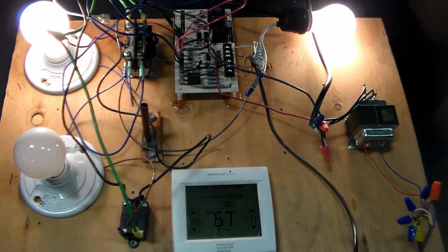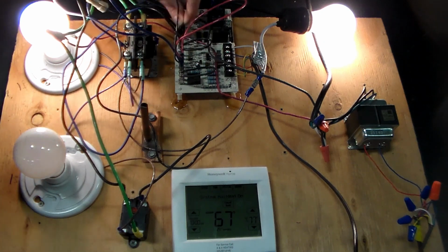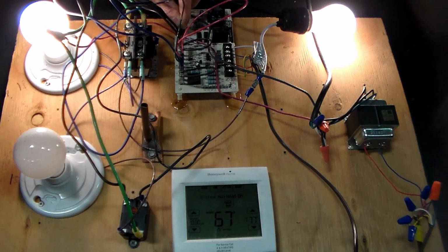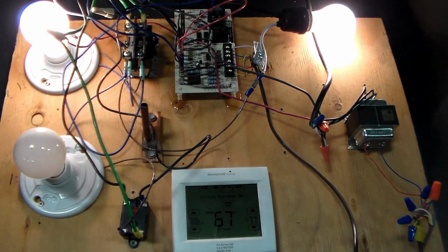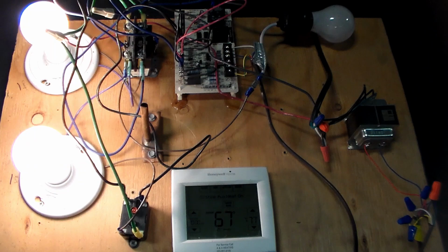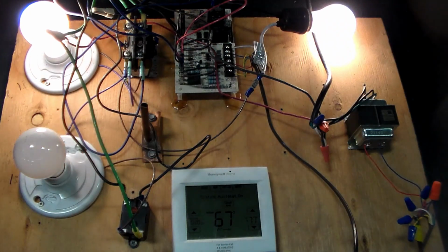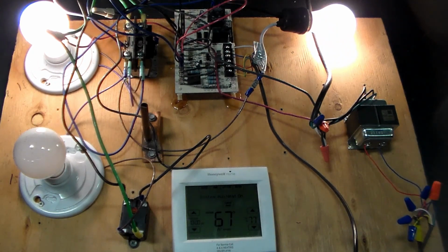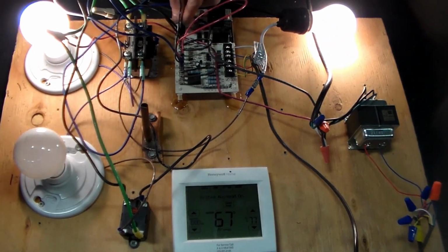And then when it goes back out of defrost, and I have it like that on purpose, it'll kick your condenser fan back on and kick your reversing valve back off. Defrost, and then out of defrost, and it'll kick your condenser fan back on. So it's going to control your condenser fan every time.